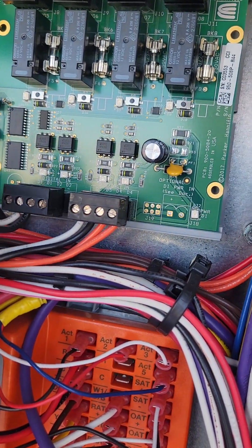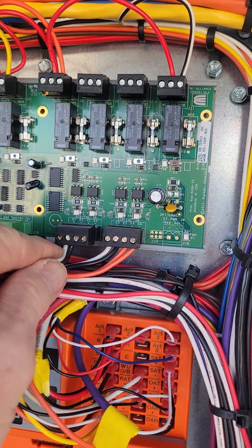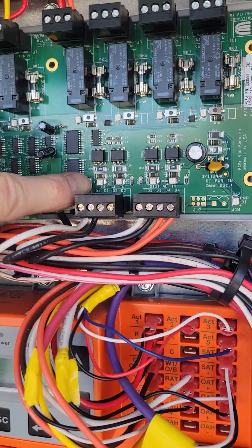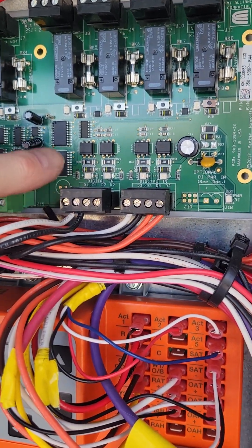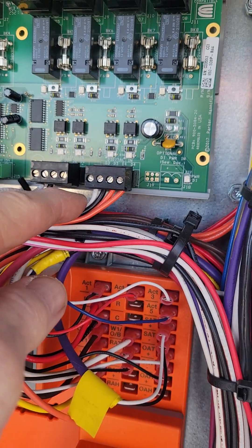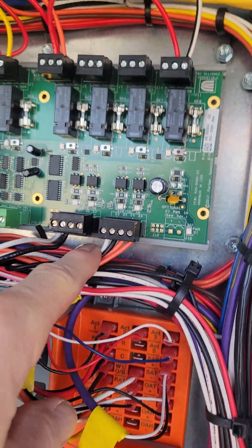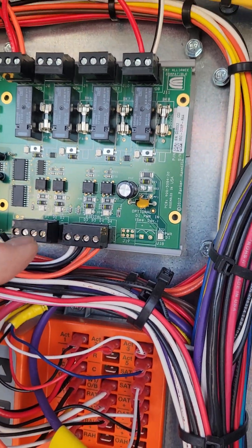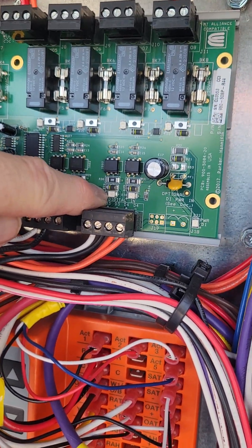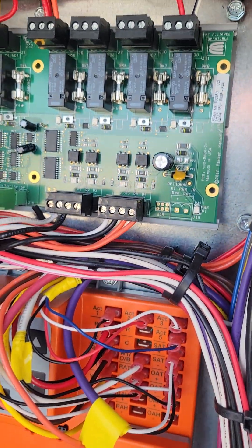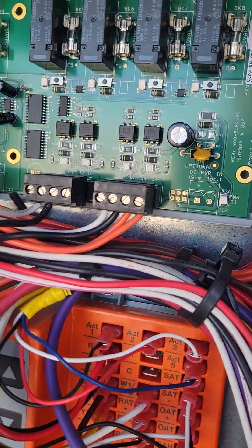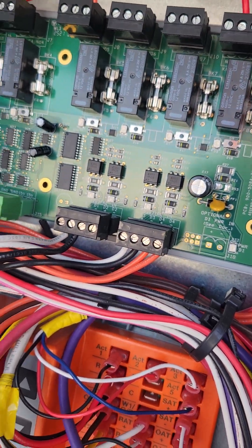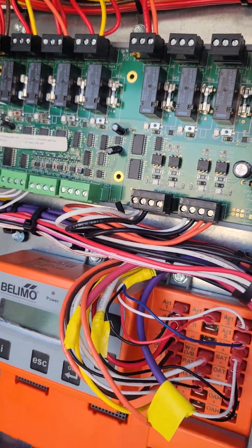So when this board is powered up and the airflow switch is closed, that little LED is going to light up. If the clogged filter switch closes, which it shouldn't because you don't want your filters to be clogged, that little light is going to light up. So these are troubleshooting tools for you to use. You can do diagnostics with these little lights.